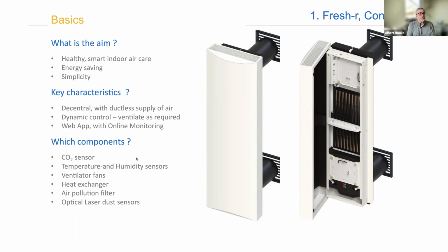It's a really, really smart thing. And so everything's variable speed. It's got a really efficient new design heat exchanger, which is basically a system of copper wires. So this is not a standard plate heat exchanger. It's a series of flat copper wires. And what that means to me is that we've got a whole new shape, because usually with a plate heat exchanger, you need a whole lot of room, a whole lot of real estate to manage that. And in this case, we've got a flat bar of copper wires doing the heat exchange. And then the only other space is really kind of 2 fan motors feeding 2 ducts.